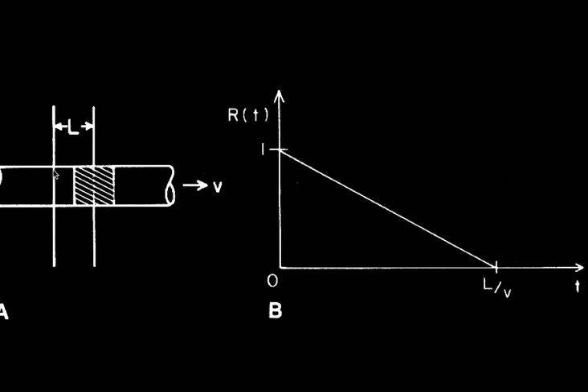If there's a time delay between the 90-degree pulse and 180-degree pulse, some of the blood is going to flow out of the volume and some new blood is going to flow in between the pulse sequences. In order to receive a signal — to produce an echo — you have to see both the 90-degree pulse and the 180-degree pulse. So if there is a lot of flow, the plug that gets the 90-degree pulse may, by the time the 180-degree pulse comes along, have flown out of the entire slice plane, and it will only see the 90-degree pulse and not the 180-degree pulse.